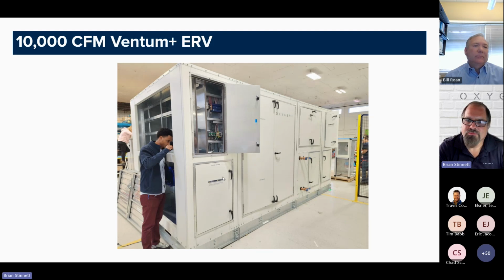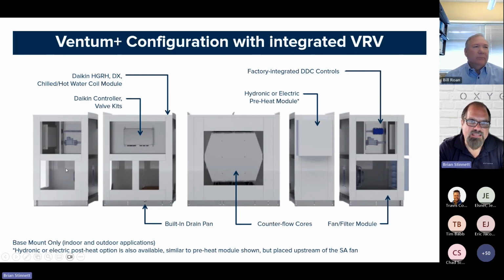So the way this is laid out is on the left-hand side, you've got a fan and a filter in that section. Next to that, you've got a coil module. So here's where you have heating and cooling coils of various types. Moving to the right, then you have those counterflow core in that stacked array, like I showed you before. You've got another preheating module. If you need a preheat, for instance, like I said, maybe I need to avoid frost, different reasons that I might need to use a preheat module. And then I have on the far right-hand side, the fan and filter module for the other airflow.